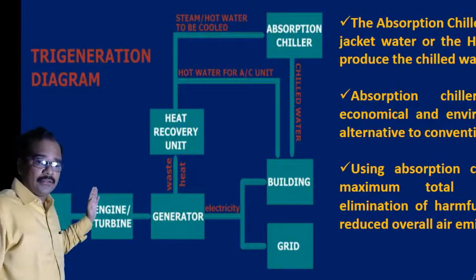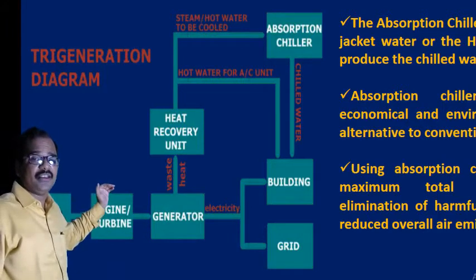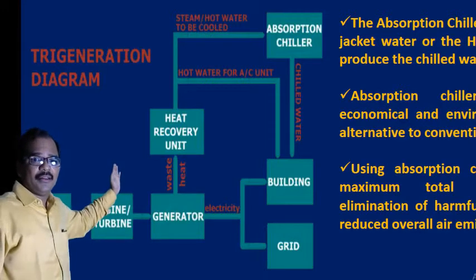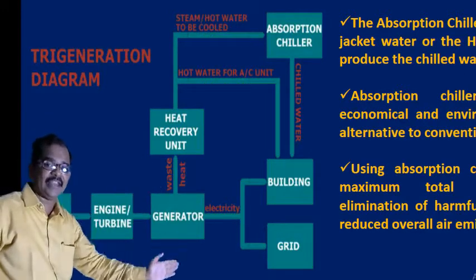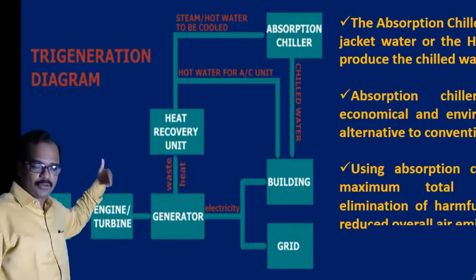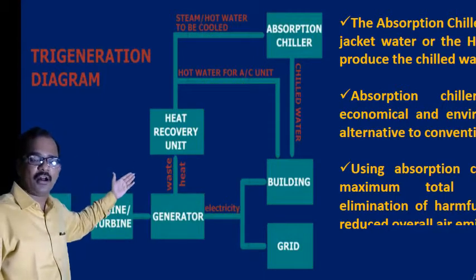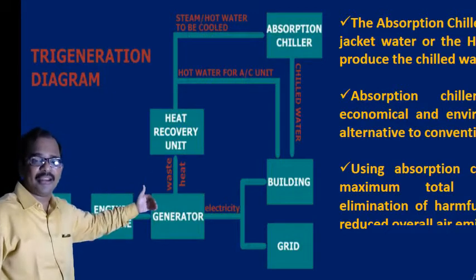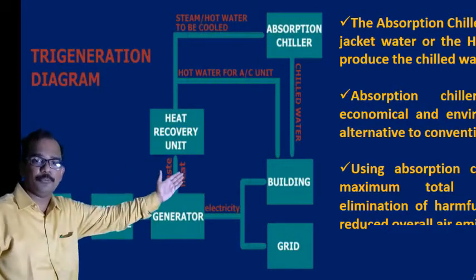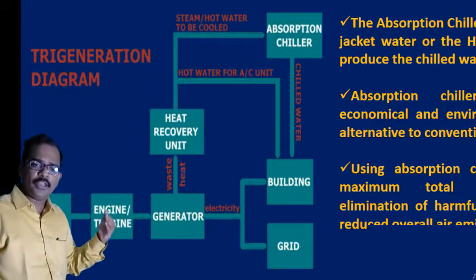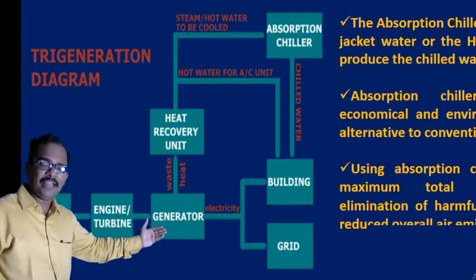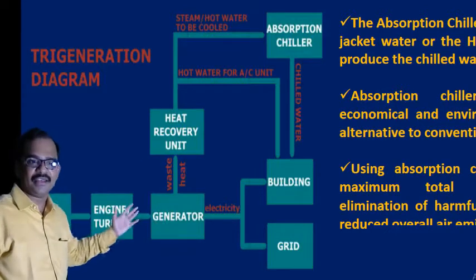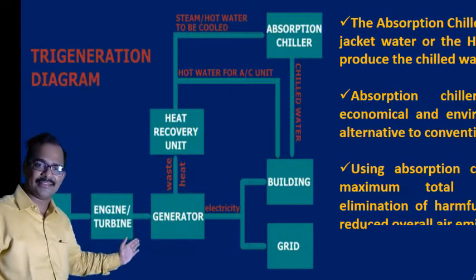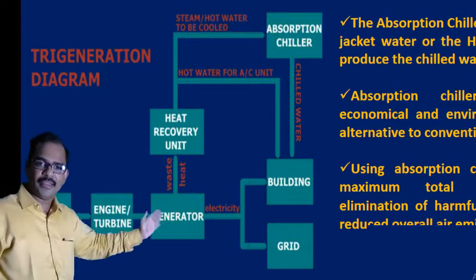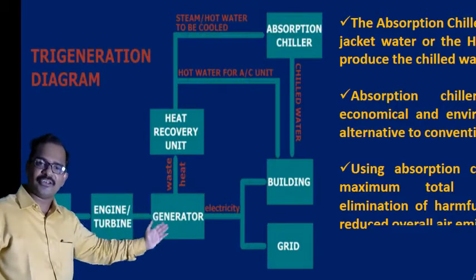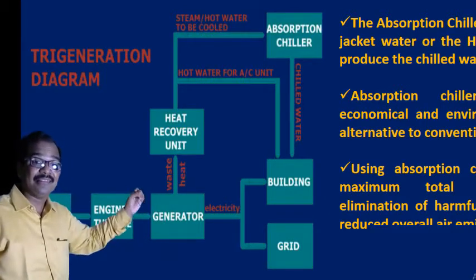And then the exhaust of this generator, that is the waste heat, is recovered in a heat recovery unit and will take the hot water or steam to the building again. So whatever is the leftover heat or the low grade heat available after converting the waste heat into thermal energy will now be utilized in the absorption chiller for producing the cooling water, and that will also be supplied to the building or facility or an industry. You can see it here, from a single fuel source, we are supplying the electricity to the building, we are supplying hot water to the building, and we are supplying the cold water to the building or facility or an industry. It is what is called the trigeneration.